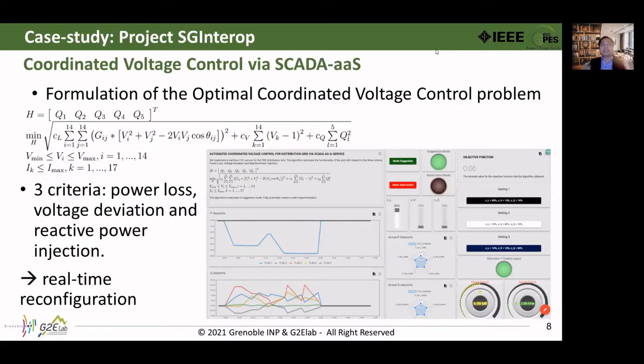The objective function of the optimal coordinated voltage control algorithm involves 3 criteria: minimizing the power loss, minimizing the voltage deviation, and minimizing the reactive power injection to the grid by the renewable energy resources. So we have here the web interface of the CVC, in which we can choose between a suggestion mode, where the algorithm only suggests the set points and the user can choose whether or not to apply them manually, and auto control mode, where the algorithm will apply the output set points directly to the PLC. And from this interface, we can also change the weight of the 3 criteria in real time.